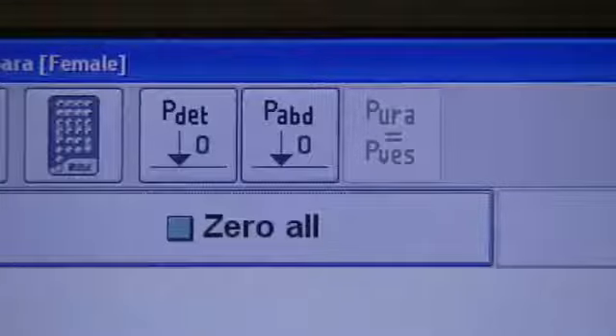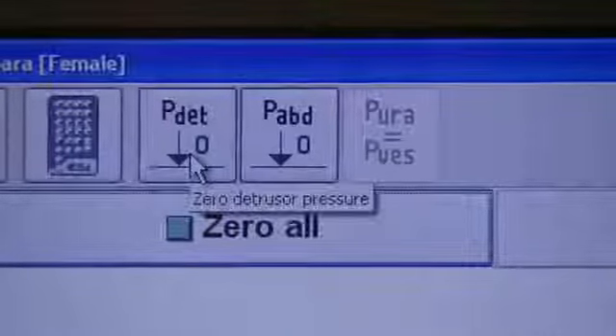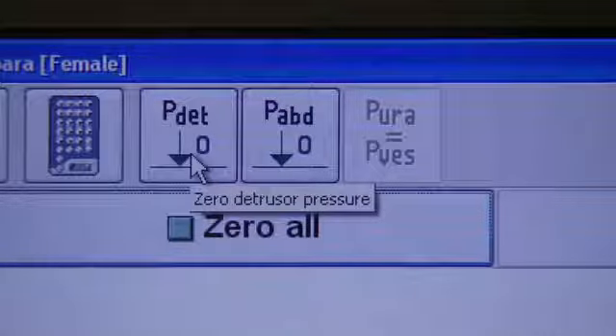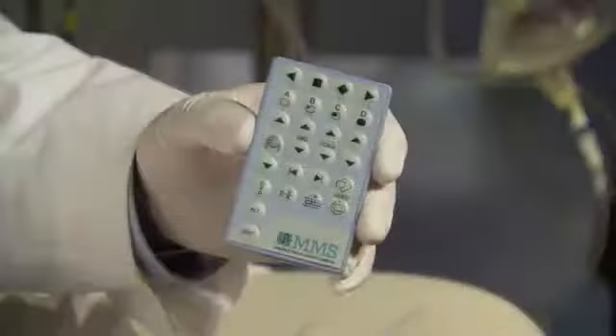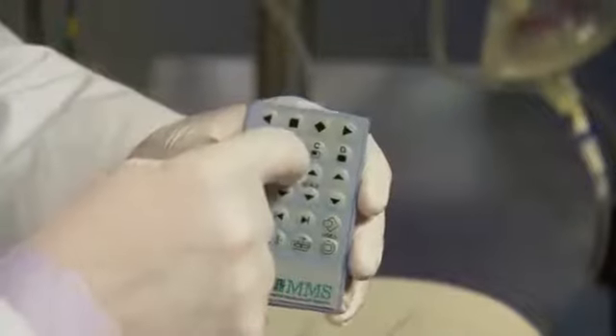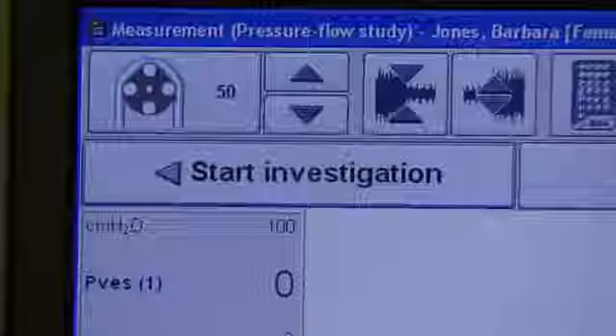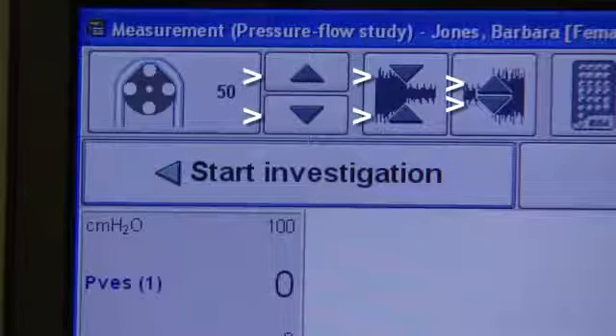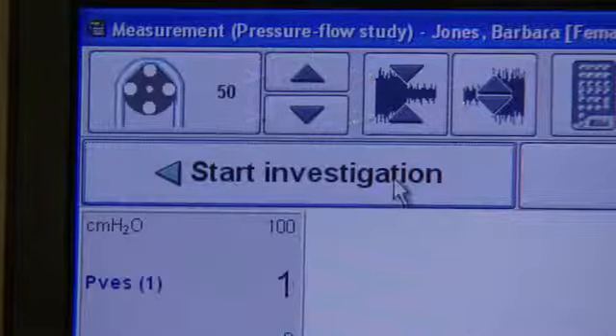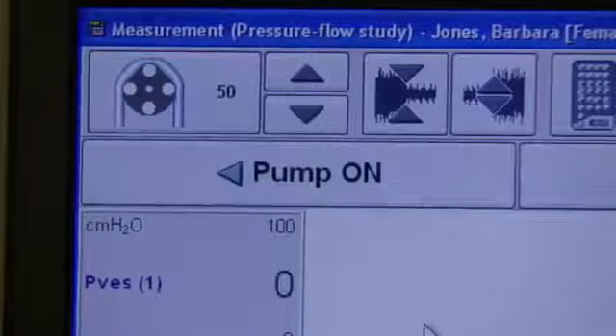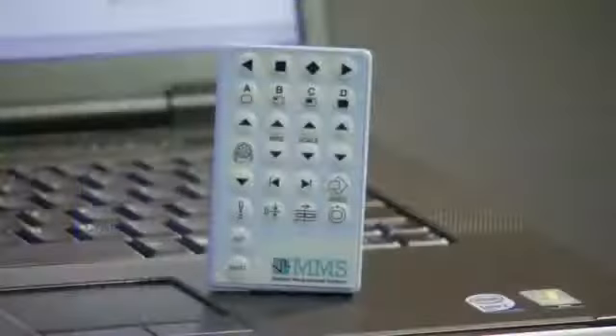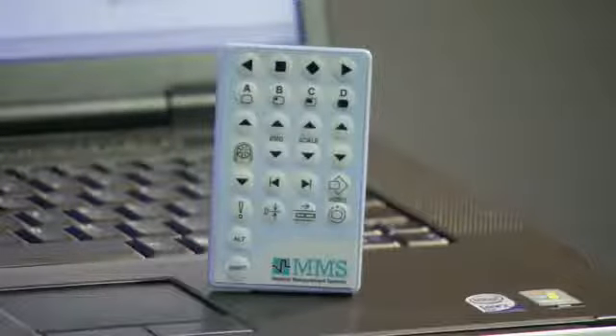Once the catheters are connected and charged, press the PDET 0 button. This will zero the detrusor pressure and even out the P vesicle and P abdominal channels. Next, adjust the EMG and water pump using the up and down arrows next to the EMG and pump buttons, either on the remote or computer screen. Lastly, press Start Investigation. During the filling phase of the pressure flow study, the wireless remote enables the clinician to complete the entire study without going to the computer.